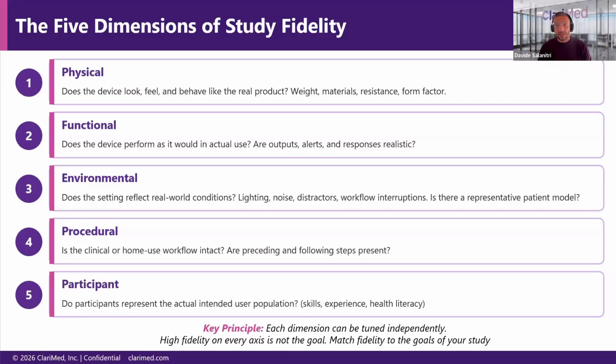Is that a risk? It may not be a risk if you just use your device at your place, in a living room. It may be a big risk if you're using it in a public bathroom. So environmental fidelity, and understanding exactly what the safety characteristics of your environment are, is super important. Sometimes you have to be as precise as possible. Sometimes you don't, depending on the device. Sometimes you absolutely do.